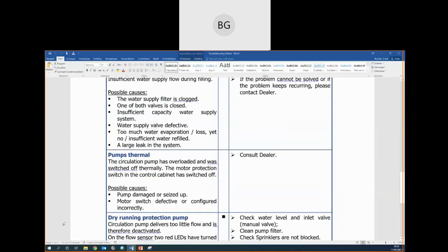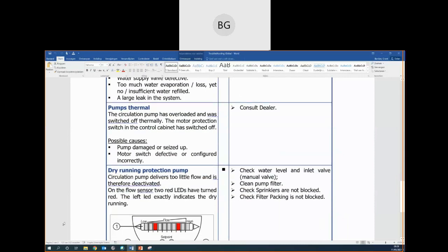Pump's thermal. The circulation pump is overloaded and was switched off thermally. This means the motor protection switch in the control cabinet has switched off. This could be due to the pumps being damaged or seized. It could be that the motor switch is defective or configured incorrectly. We have here in the manual, consult the dealer. That is to say, consult an electrician who can give you a correct assessment of what's wrong there.